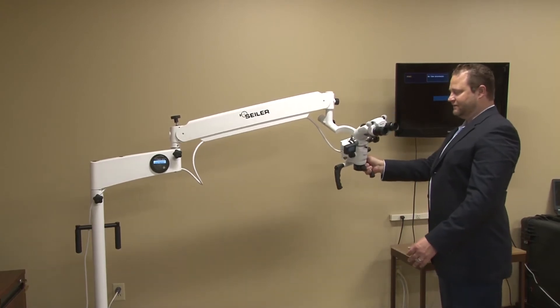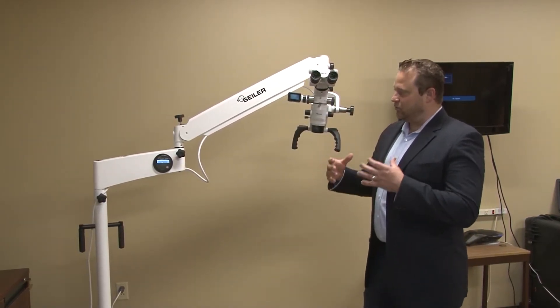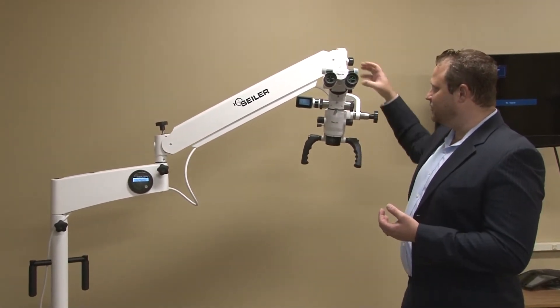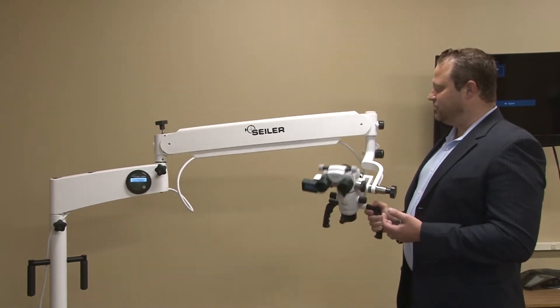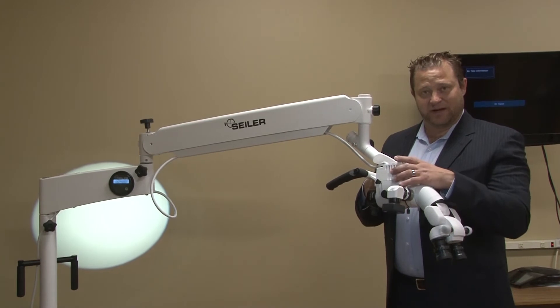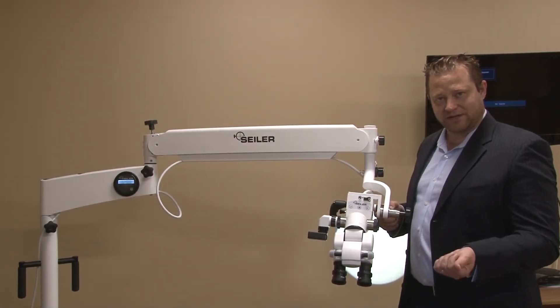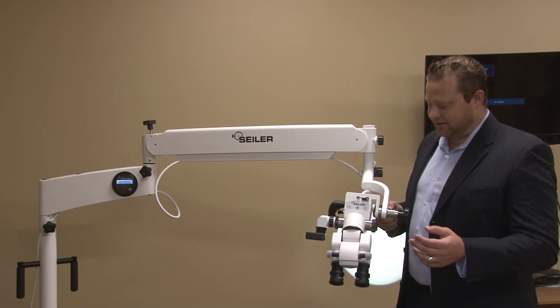One of the biggest things we have done with the new Alpha Air is make it one of the lightest microscopes on the market, with a new sleeker design. Movement from the optical pod and arm is absolutely flawless. We have the LED directly on the optical pod, and we have the brightest standard light on the market at 150,000 lux, which comes into play at higher powers of magnification — because the higher the power you go, the darker it gets, so you need that extra brightness.